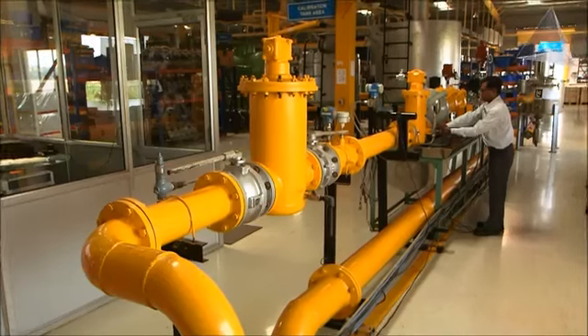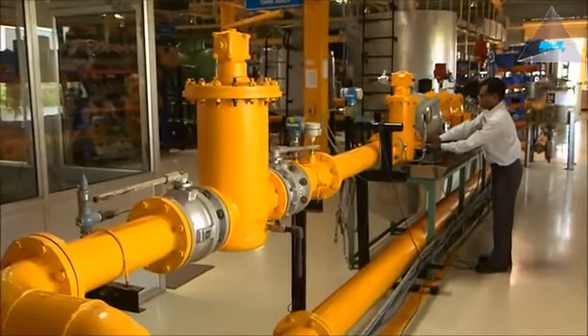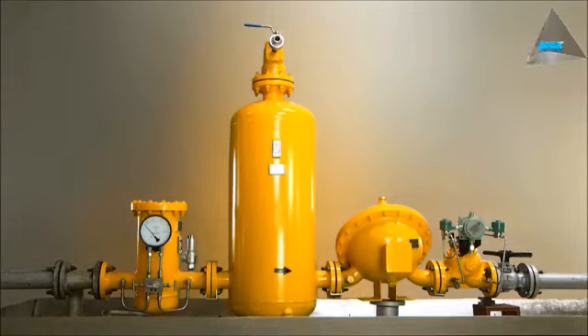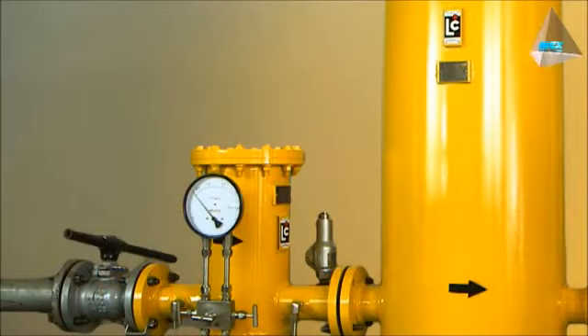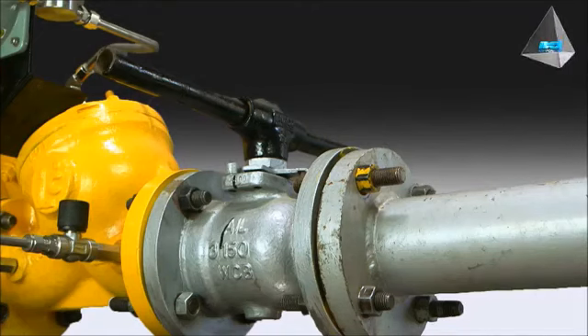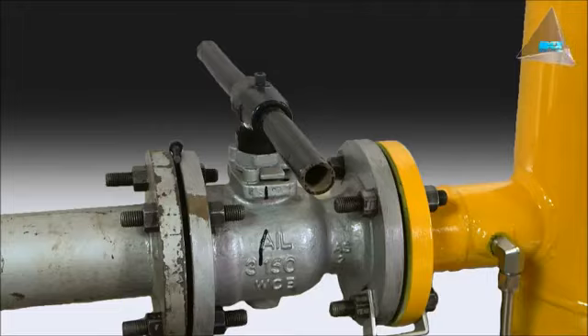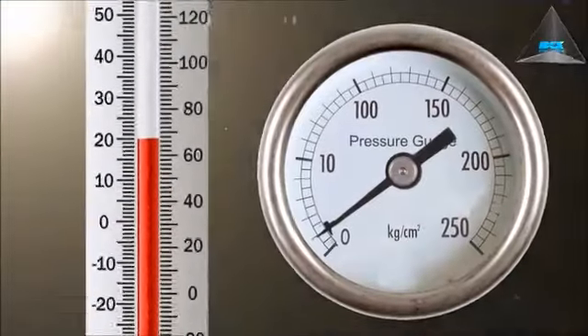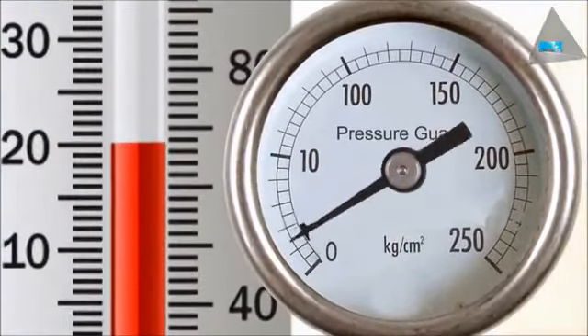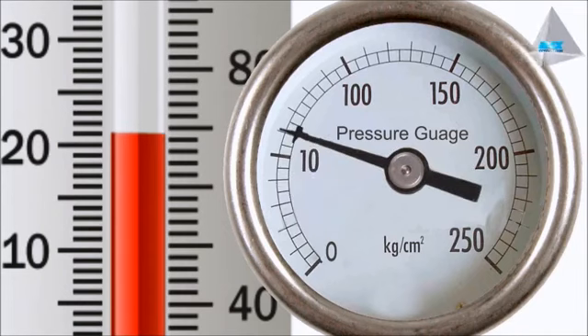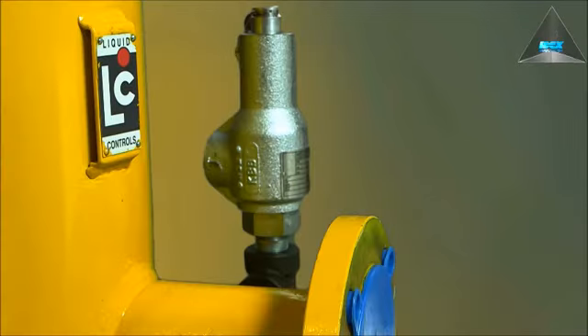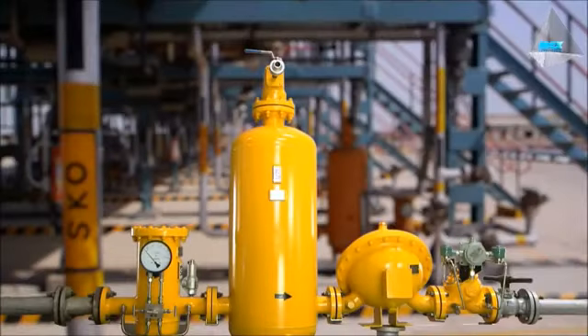Care must be taken in the installation to not create zones where the product can be locked between two closed valves. If lighter petroleum products are trapped between two valves, and if the temperature increases by 1 degree Celsius, the resulting pressure change will be in excess of 8.8 kilograms per square centimeter. A thermal relief valve needs to be provided in such installations, and the proper path of the thermal relief would be typically towards the upstream valve.